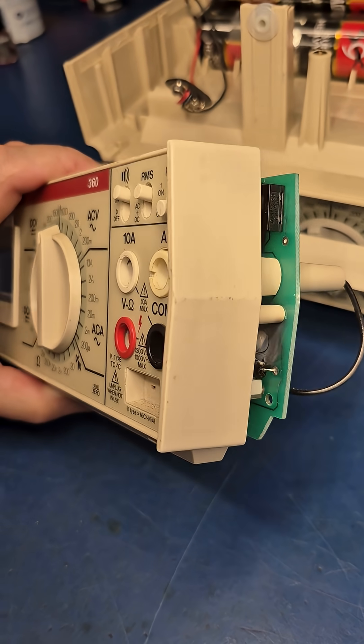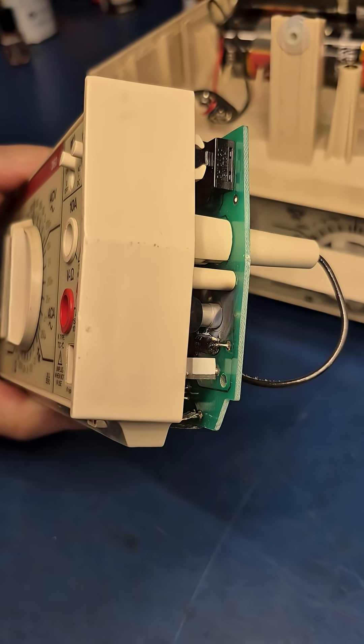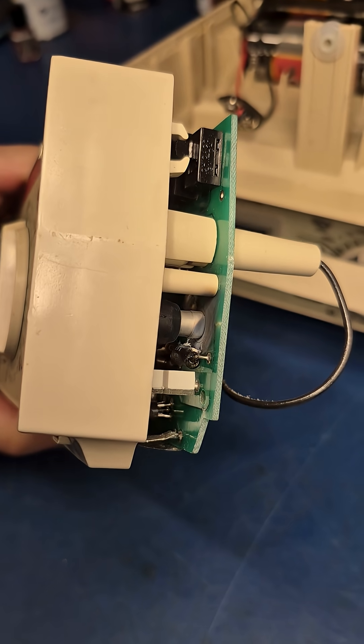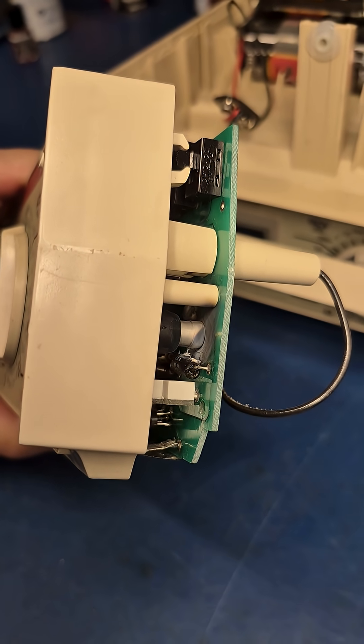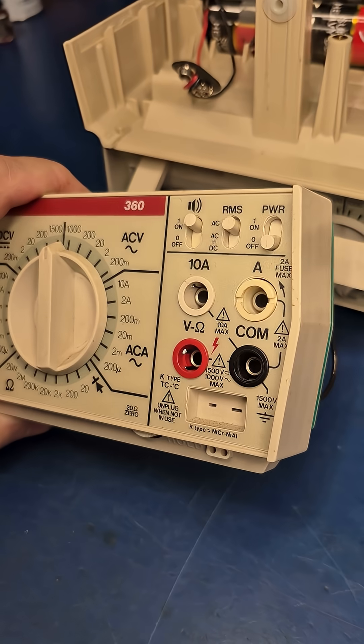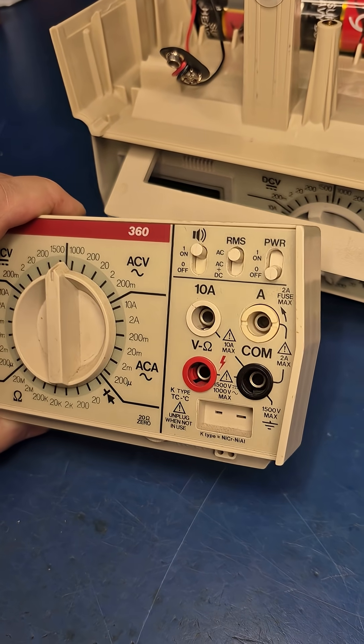So I pulled the front panel off of the Beckman and I could already smell that burnt electrical odor. Looking down there by the negative post, you can see she's been doing some arc welding. Obviously somebody had exceeded the input voltage to this meter, or there was contamination.